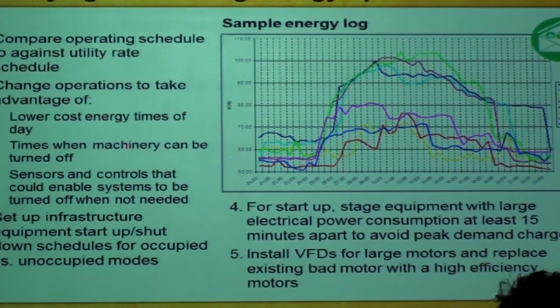Change operations to take advantage of lower cost energy times a day. Sometimes they will charge you lesser amount of money from a certain time, let's say from 12 midnight to 6 a.m. If they're doing that, then you should take advantage of those times. Times when machinery can be turned off. When can I switch off the HVAC units? Not needed, etc. Sensors and controls that could enable systems to be turned on and off. Motion control, automation systems, etc. Set up infrastructure, equipment startup, shutdown schedules for occupied versus unoccupied modes.